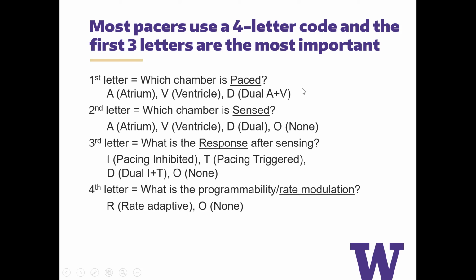So this is the configuration for determining what the mode is. You often hear about these 3 letters like VVI or DDD. The first letter tells you which chamber is paced. Is it the atrium, the ventricle, or is it both? The second letter will tell you which chamber is sensed. Is it the atrium, the ventricle, is it both, or is it none? The third letter tells you what is the response of the device. What is it supposed to do after it senses a signal? Does it inhibit pacing? Does it trigger pacing? Does it do both, inhibit or pace? Or does it do none?